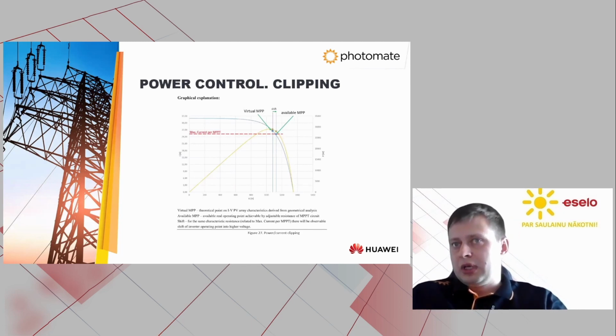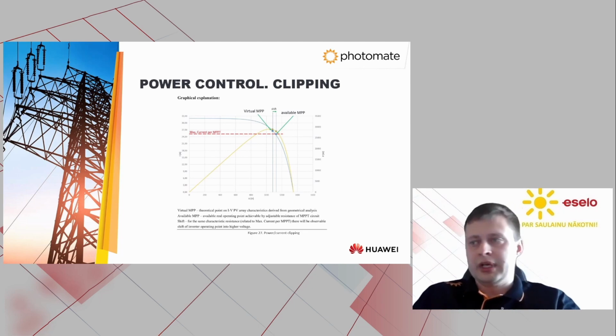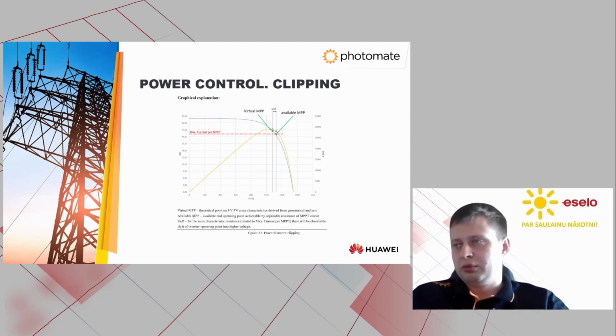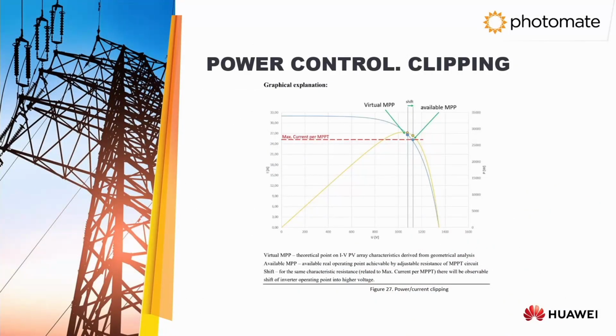Very common question: if the inverter gets limited, is all the power going to be dissipated as heat? So I wanted to answer this question. No, it is not dissipated as heat, because the maximum power point controller is responsible for finding the maximum power point. But in case the inverter power must be clipped, it just moves away from this maximum power point. As shown in the figure, the voltage increases a little bit, then the current decreases, and the power also decreases. That is how inverters clip the power.